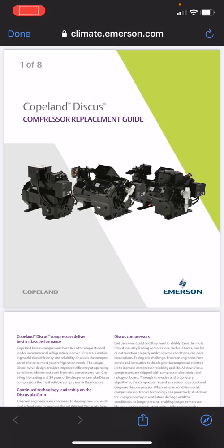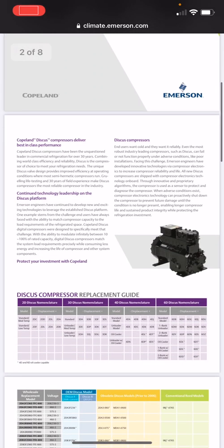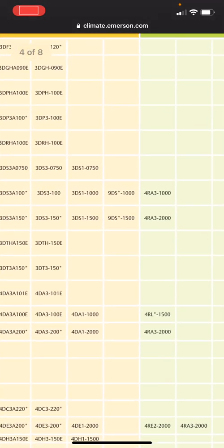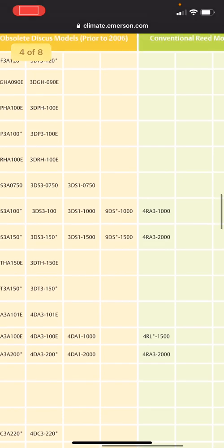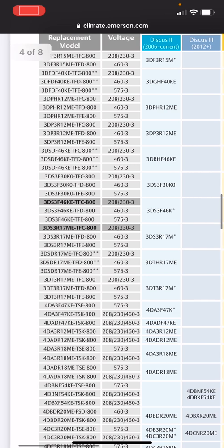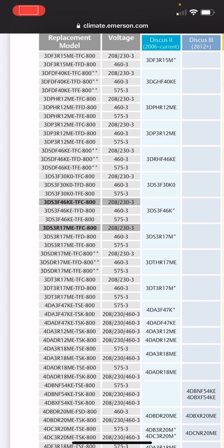Copelametic is our original design, we upgraded back in the 80s to Discus, these are more efficient designs. But if you have a failed reed compressor right here, just a quick example, say you have a 4RA3-1000, if you scroll across, a 3DS-3F46KE TFC depending on your voltage, could be a TFD or a TFE, that would be the replacement model to put a more efficient compressor in your system, in your customer system. What you need to be aware of though, there are a few models between let's say 10 and 20% where there may be adjustments. Maybe you need to change the piping configuration, maybe the feet need to be moved a little bit. This is how you work with your Copeland authorized wholesaler and say listen, I want to upgrade from my old Copelametic reed compressor to the new Discus more efficient compressor, can you get me the drawings to see if anything needs to be changed?